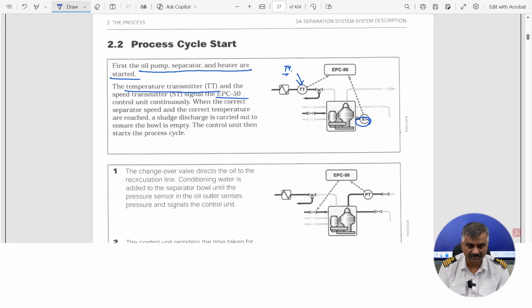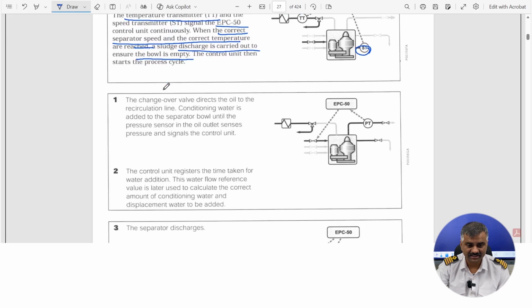And then the purifier separator also has a rated speed, right? That speed sensor ST, speed transmitter, is giving a signal to the EPC 50 that the correct speed has come. So when the correct separator speed and correct temperature are reached, the first thing is the sludge discharge will be carried out to empty the bowl. Any contents before the operation have to be discharged out. That happens in Mitsubishi also. Before giving the purifier start, the bowl has to be emptied. Okay, the first discharge, the desludging, has taken place, then the process for purification will start.